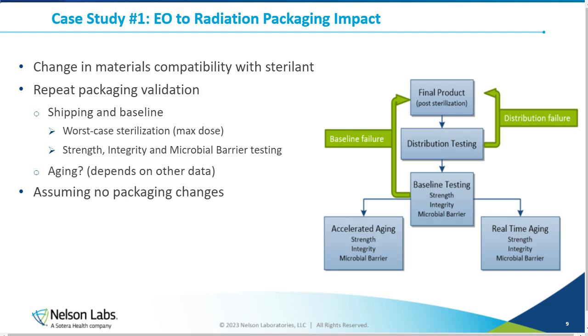Then you're going to do baseline testing for strength, integrity, and microbial barrier, and make sure that somewhere along the line with sterilization or distribution, you didn't get any holes or breaches or integrity problems with your packages. And then you're going to age the product to the end of its expected shelf life and repeat that testing again. If you are switching modalities from EO to radiation, how does that really affect this validation?